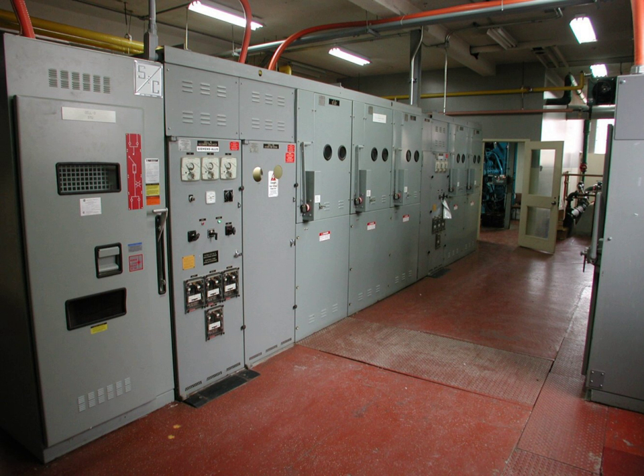A large electrical room may have extensive provisions for grounding and bonding enclosures of electrical equipment to prevent stray voltage and danger of electric shock, even during faults in the electrical system. Lightning protection requires different measures than protection from power frequency faults. Electrical rooms may have electromagnetic shielding to prevent interference to nearby sensitive audio or video equipment. In large facilities, access control systems may control admission to the room.